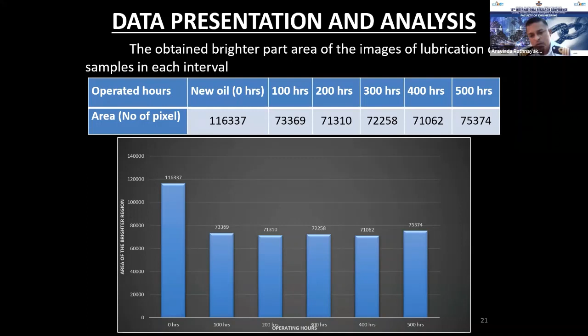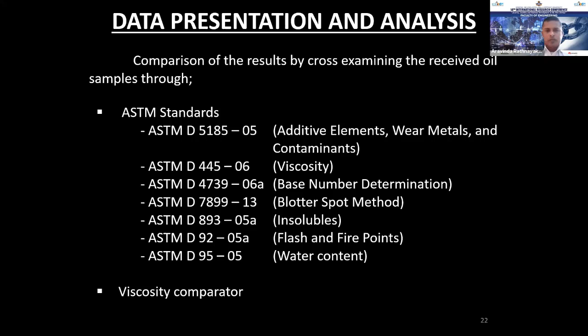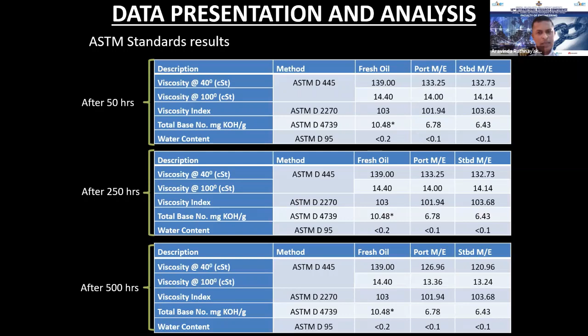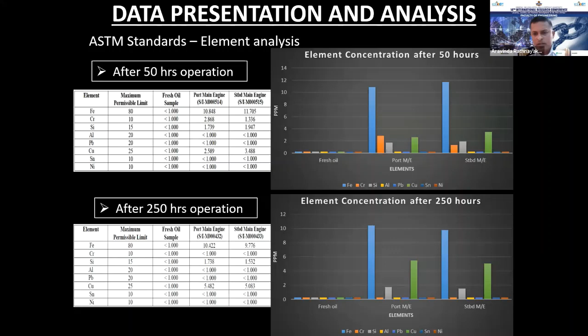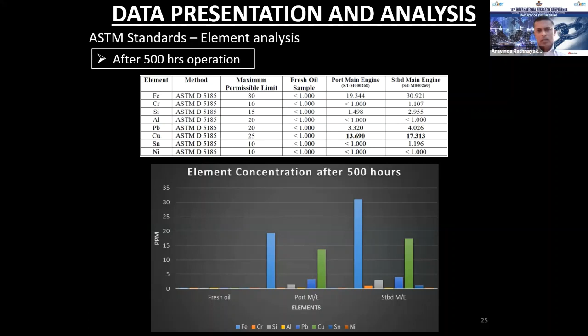Now we have to check whether those results are correct or wrong, because we use the same oil, by checking through the ASTM standards and also the viscosity comparator, to see whether the results are accurate or not. Through the ASTM standard, I have taken the readings for 500 hours used oil samples, and the properties were within acceptable limits. Likewise, in the ASTM standard analysis, for 50 hours, 250 hours and 500 hours of the same used oil, those readings were within limits. I have also checked these used oil samples through the viscosity comparator, and these are the readings that I got. All these lubrication oil samples were within acceptable limits.